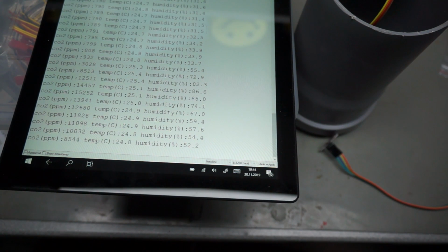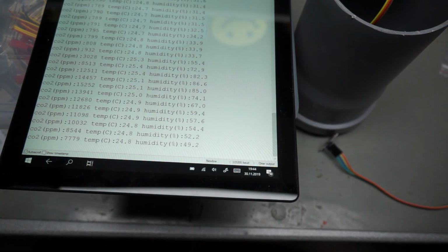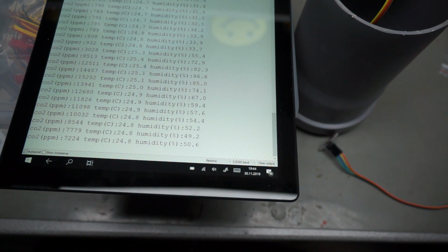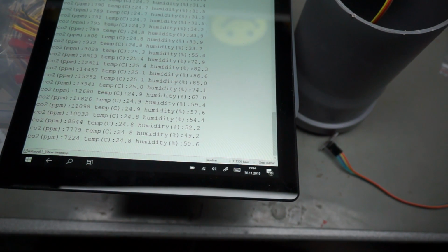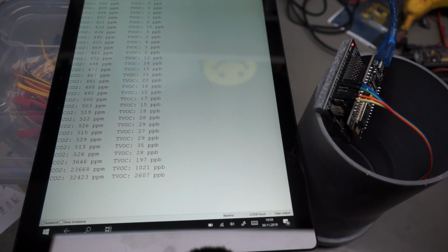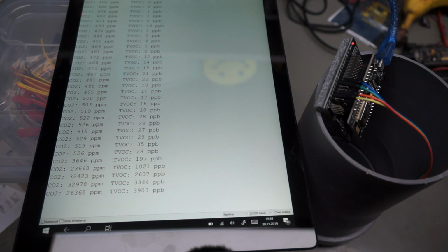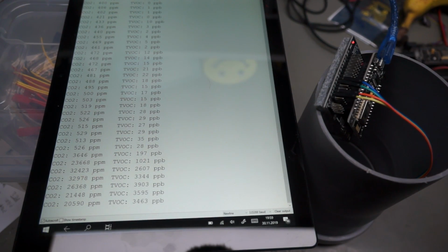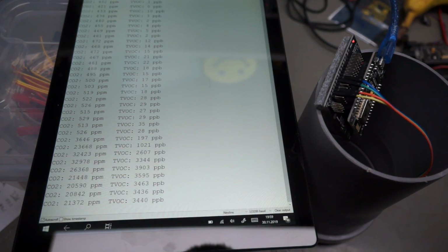As you see, my exhaled air contains a lot of CO2, and it takes a few seconds until the CO2 sensors read these high values. The VOC sensor reacts much faster. This can be useful for specific applications where speed is essential.